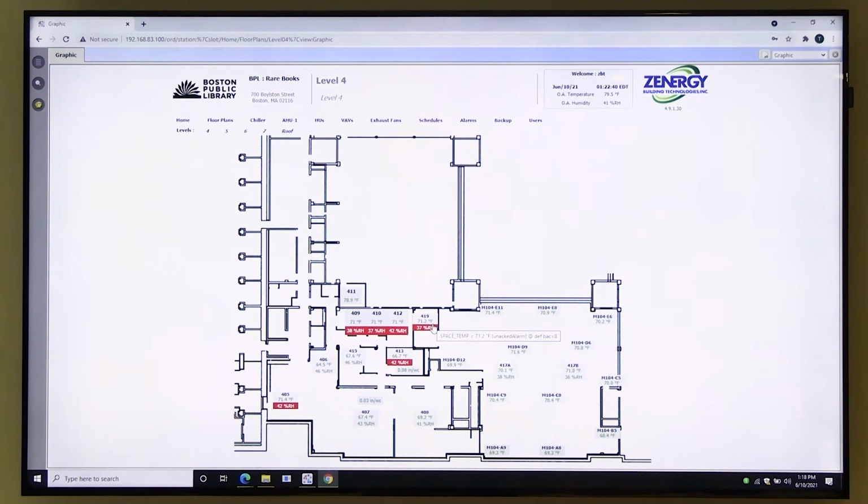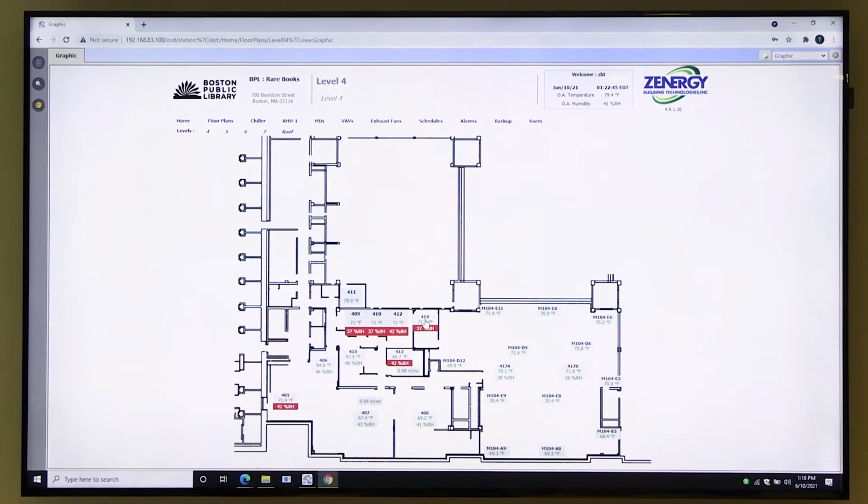That is the actual sensor wired on the wall that's going to communicate back to the system. As you can see, the red background, we'll go over the background colors at some point, means alarm, so technically these values are an alarm because the humidity is outside the acceptable range. This is being looked at, so this is a known issue that we're addressing, but just bear in mind.